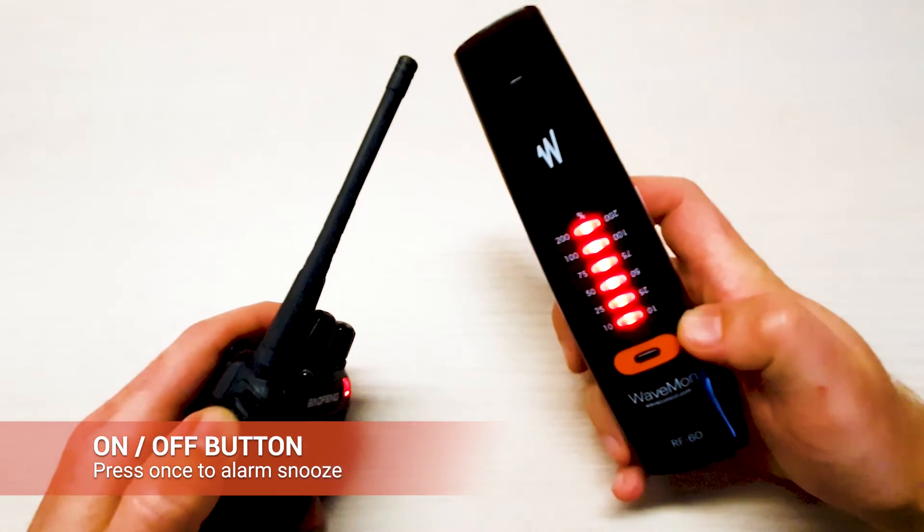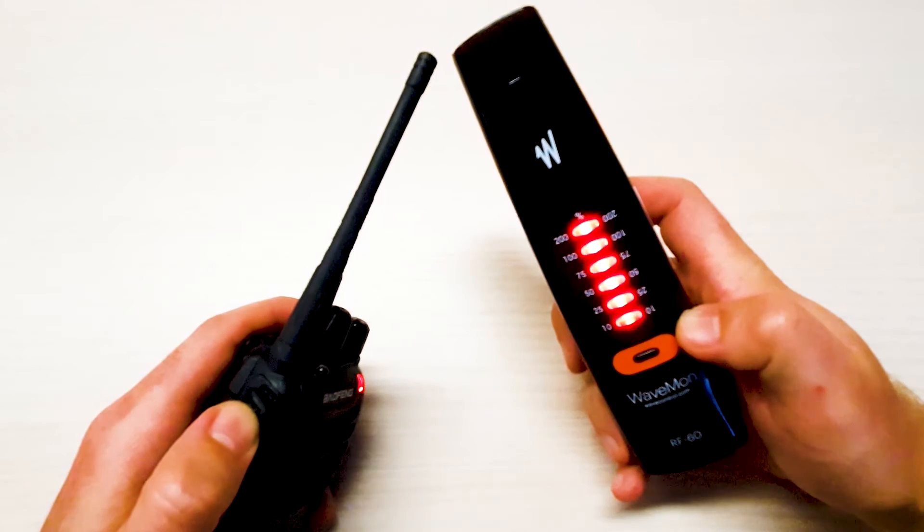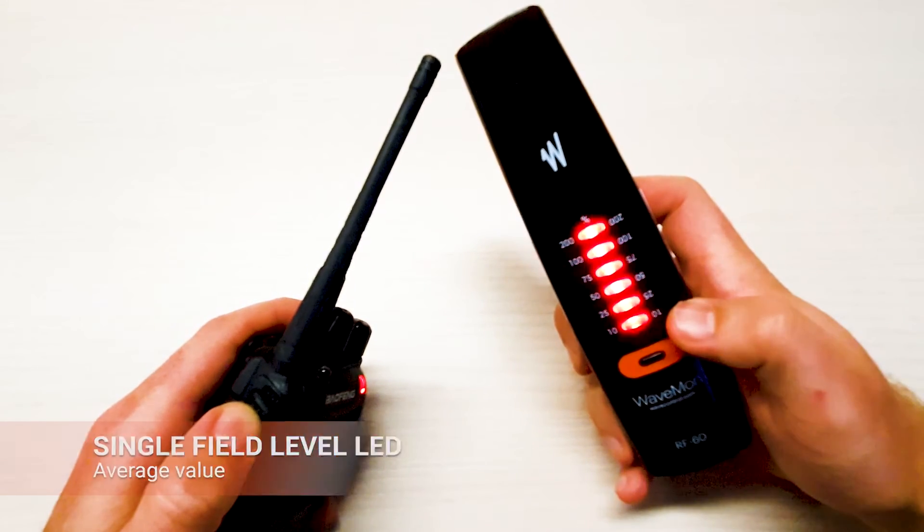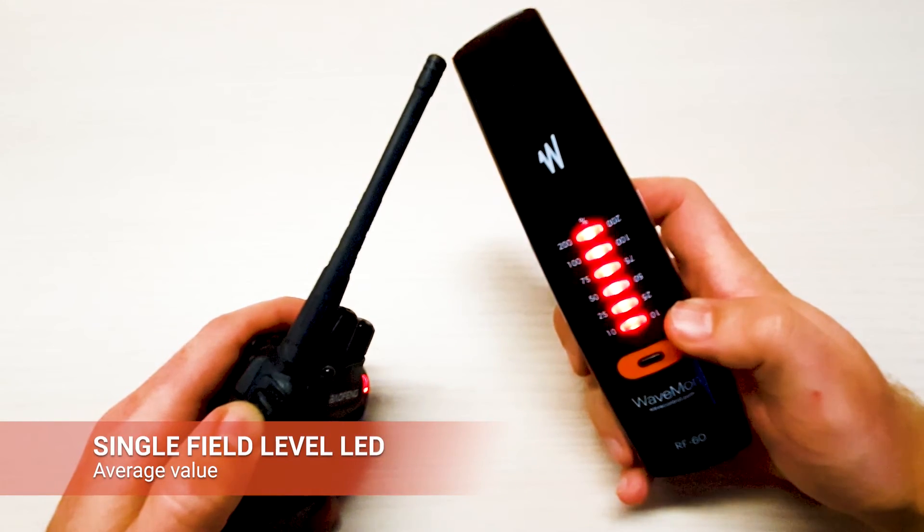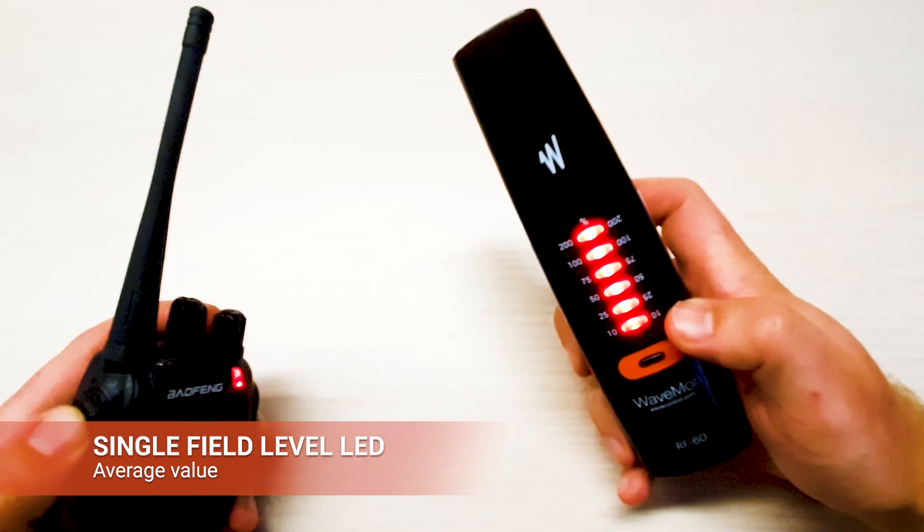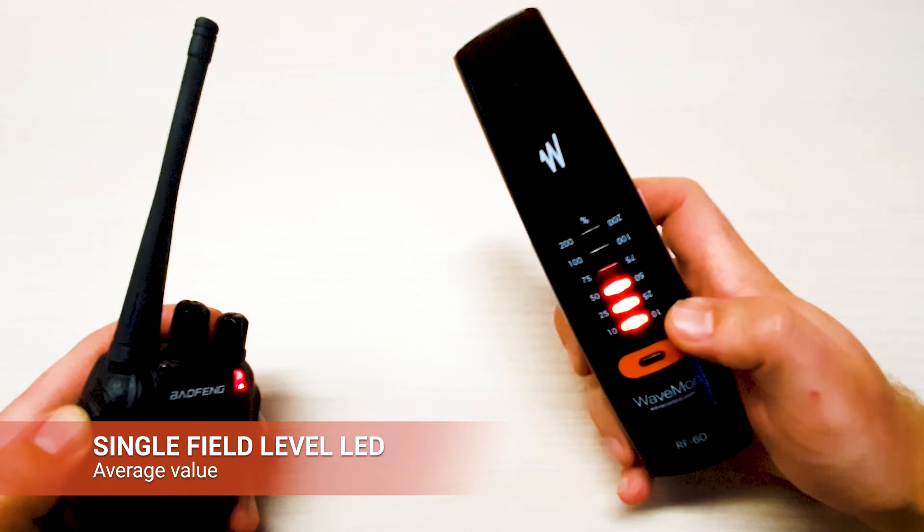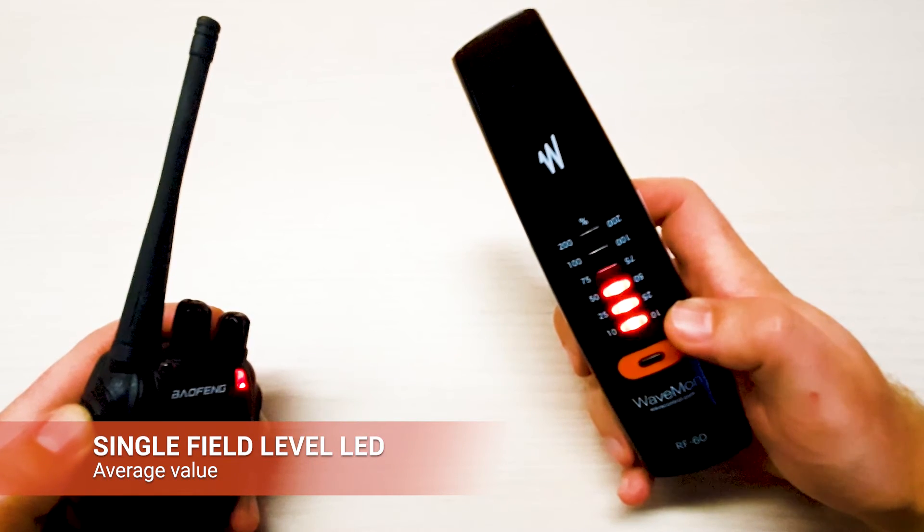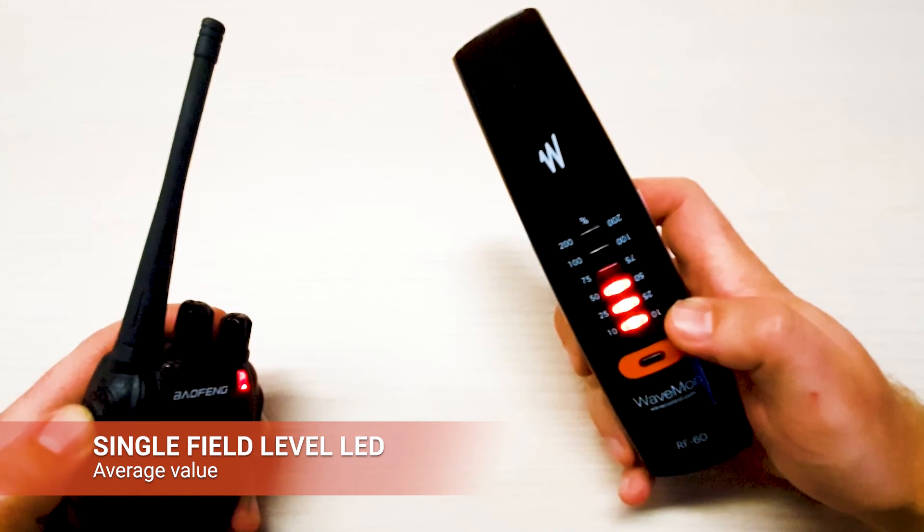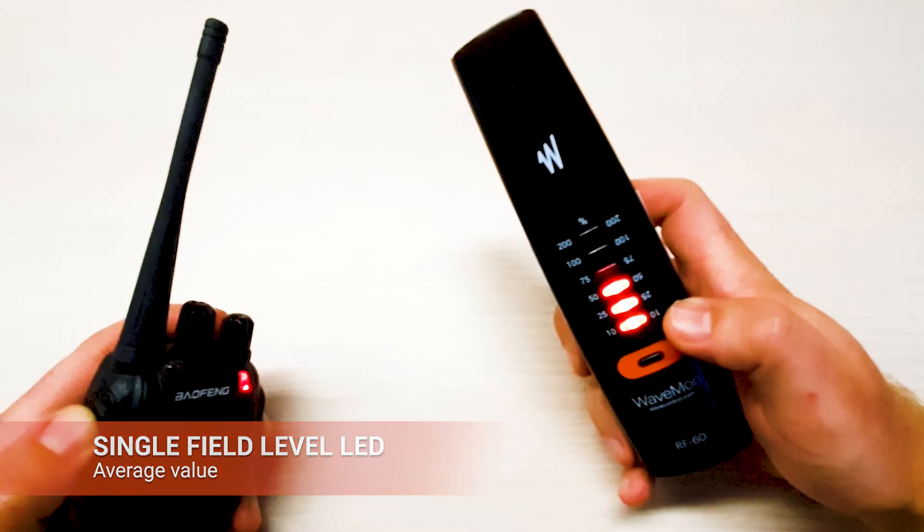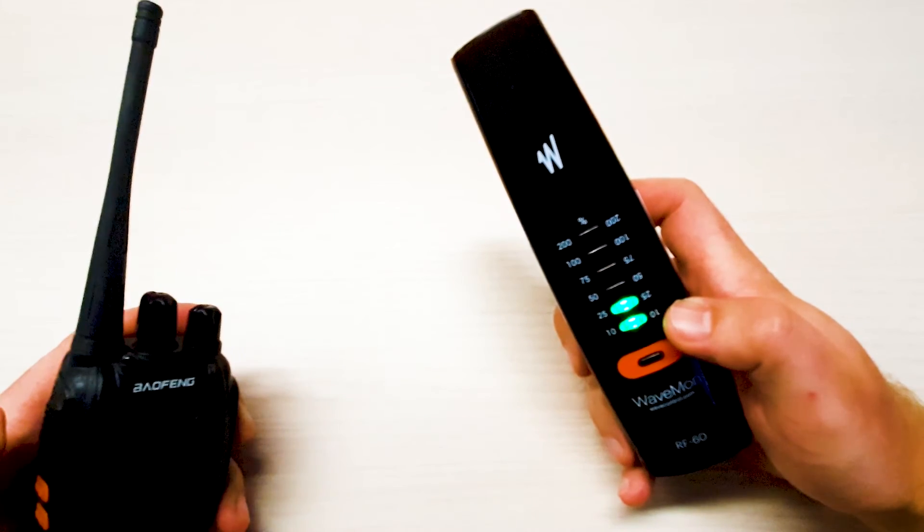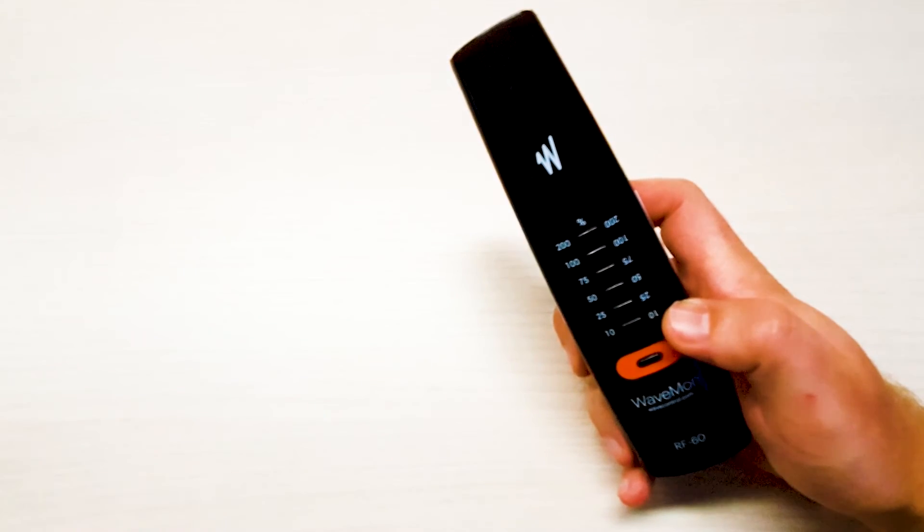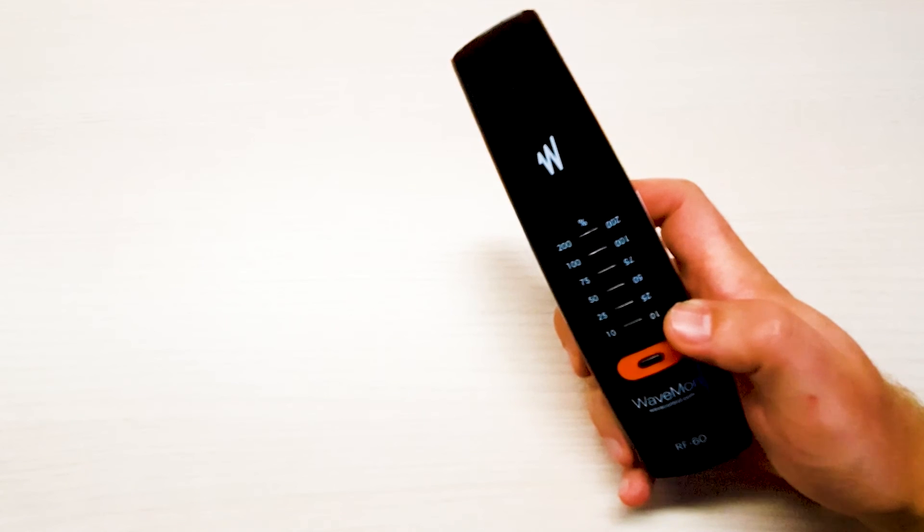We can see also that the unit not only shows the instant value but shows the average value. So right now the unit measures 50% instant value and 25% average value. If we stop the RF we still can see that the unit measures 25% of the average value.